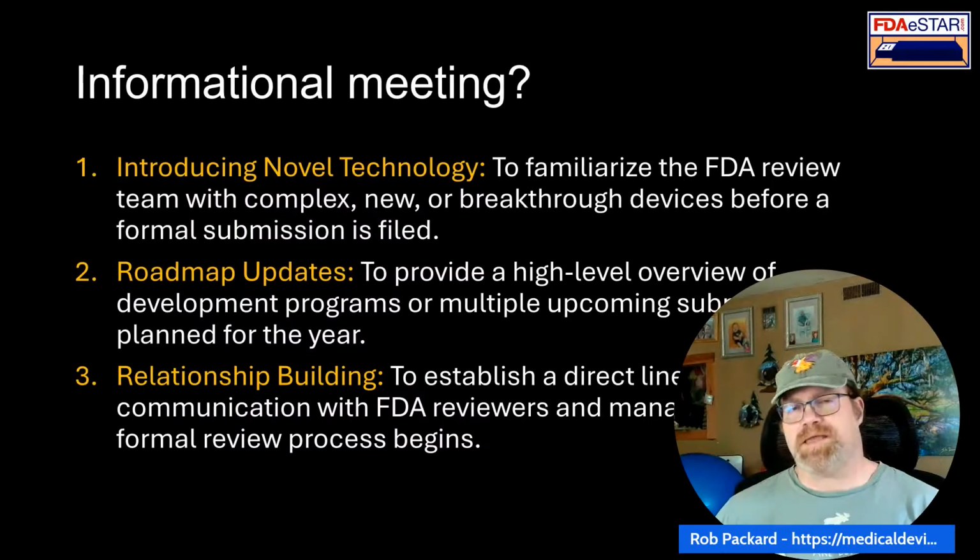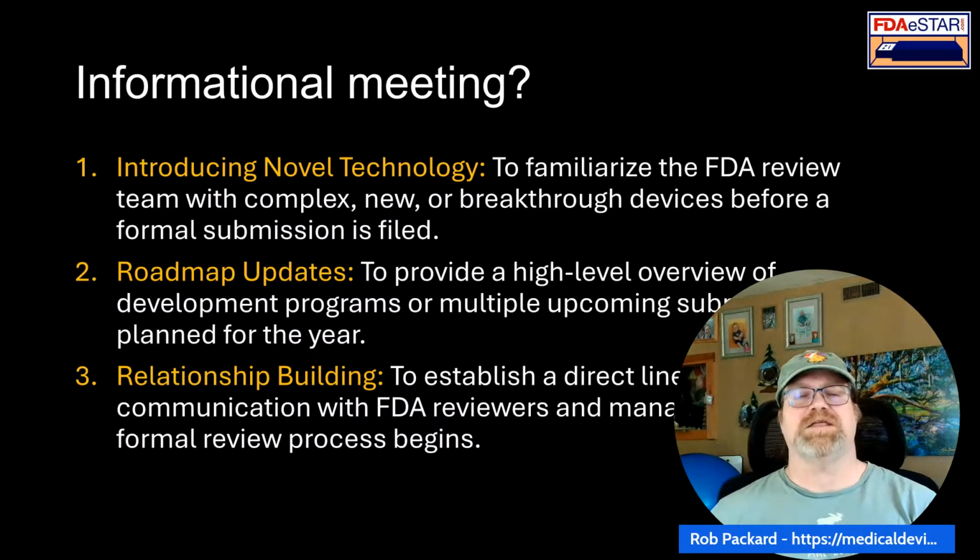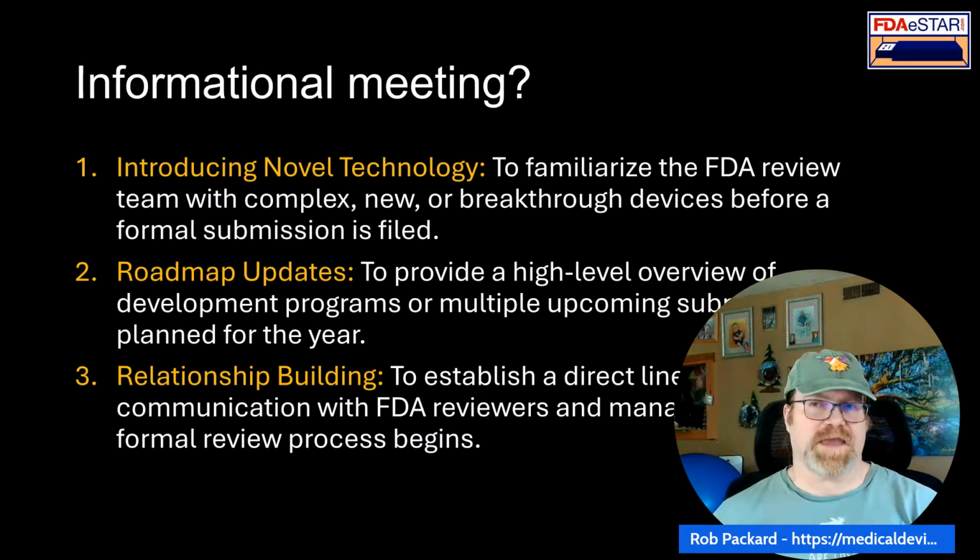So you want to explain that to the FDA and explain it's going to be a platform technology. And you might even explain, we're choosing this one first because we think this will be the easiest to get through the FDA and it's low risk. So it gives the FDA an opportunity to review the technology and get your first 510(k) clearance or de novo.